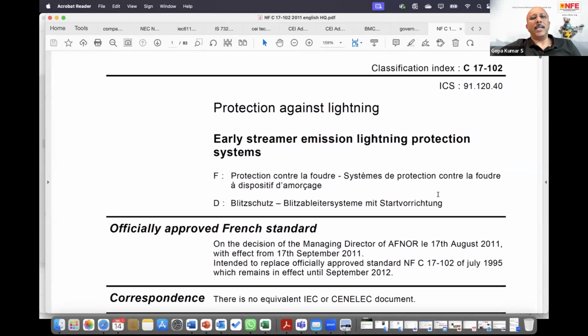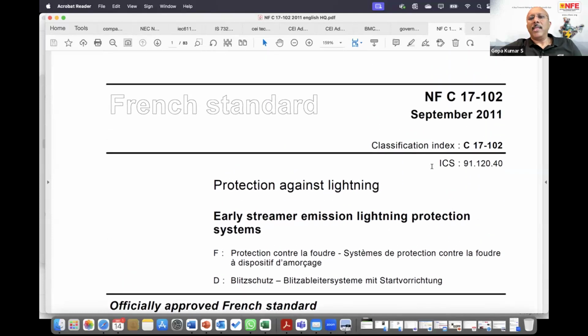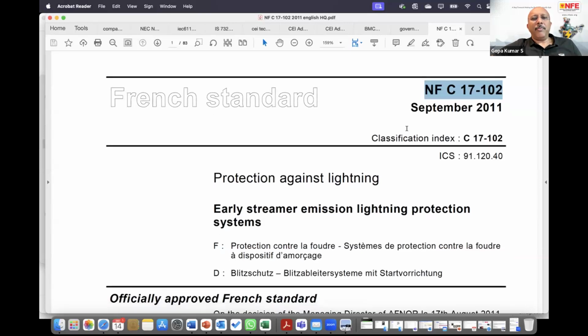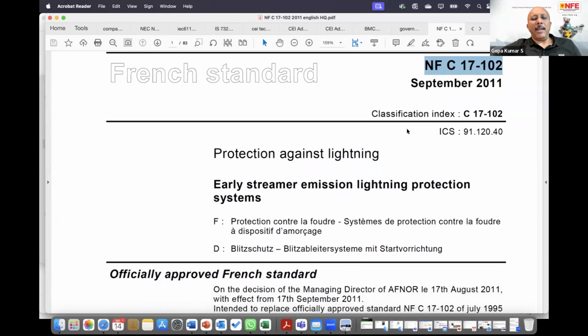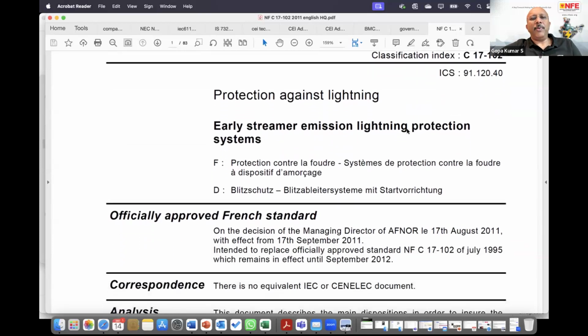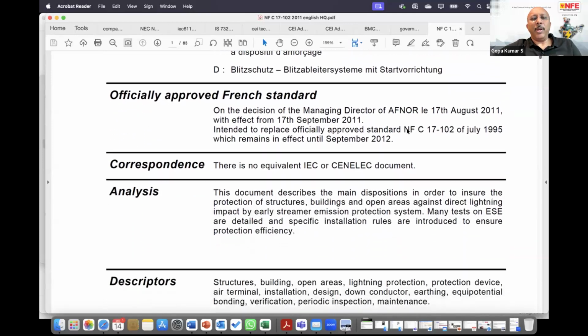Let us look at this case. In France, the lightning protection standard is not NFC 17102. It is NFC EN 62305, which is nothing but the same standard which we follow in India, 62305. All the European nations following EN standards is mandatory.